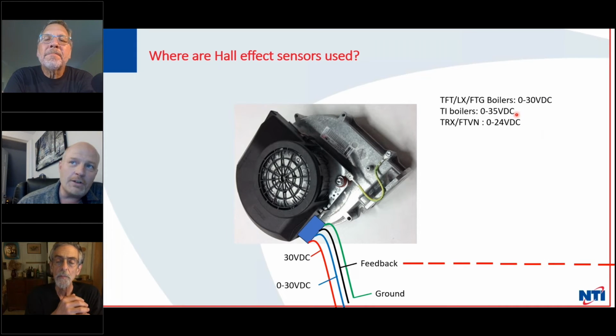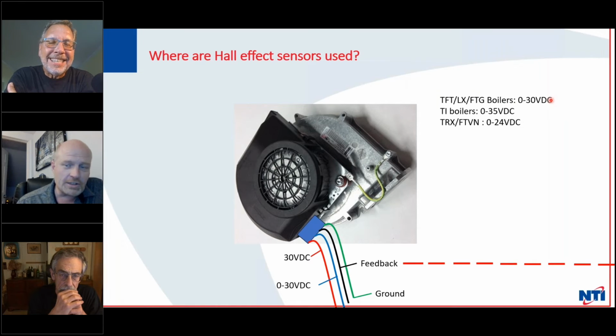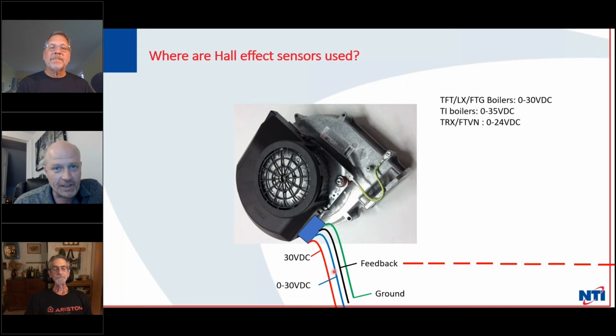Up on the right here, I've given you a little bit of a cheat sheet. TI series boilers, the blowers are controlled with 0 to 35 volts. TRX, FTVN, it's 0 to 24 volts. TFT, LX, FTG boilers, anything using a SOLA control. So if we have any Laars fans out there and you've got a SOLA, it's 0 to 30 volts is the control signal. And what your blower does is it looks at this 30 volts and compares it to the secondary voltage, the variable. And the difference between the two drives the fan. So if the difference between 30 volts and 15 volts, let's say, is 15 volts, your blower is going to run at about 50%.